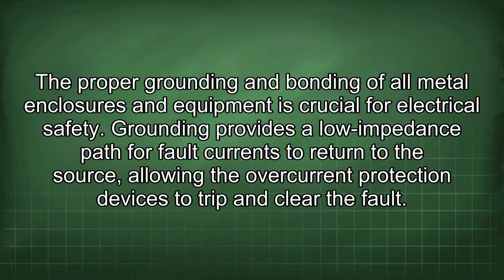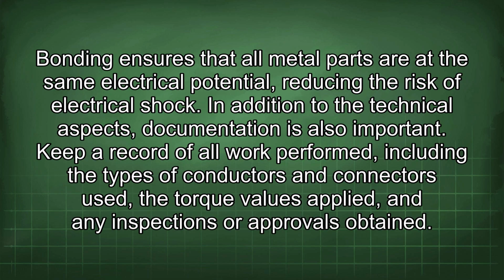The proper grounding and bonding of all metal enclosures and equipment is crucial for electrical safety. Grounding provides a low impedance path for fault currents to return to the source, allowing the overcurrent protection devices to trip and clear the fault. Bonding ensures that all metal parts are at the same electrical potential, reducing the risk of electrical shock.